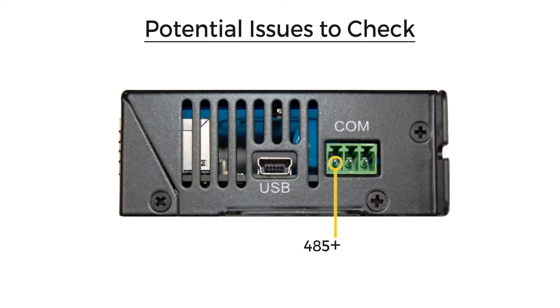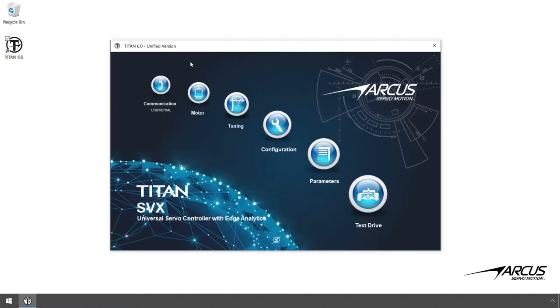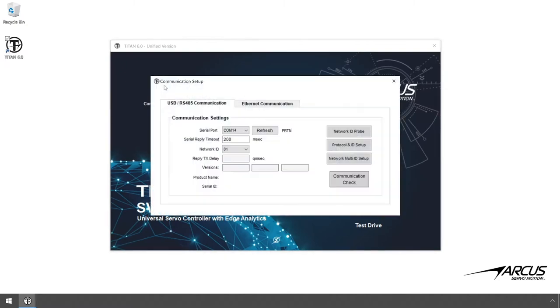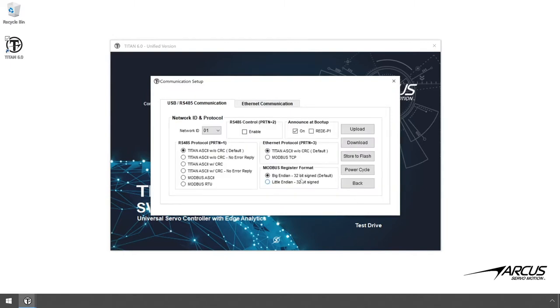Make sure that 485 plus, 485 minus, and ground pins are connected correspondingly. Second, check the network ID and protocol. You can check the settings by opening the protocol and ID setup screen. When the Titan is shipped from the factory, the default network ID should be 1 with default protocol setting.